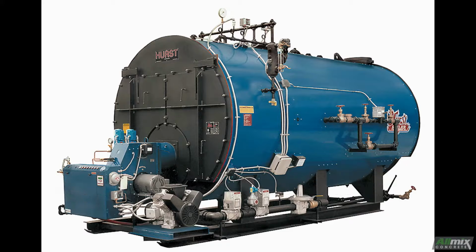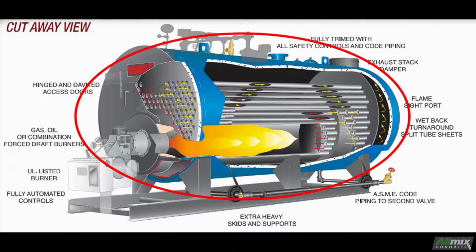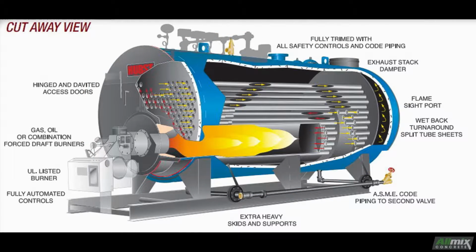The fire tube boiler, which we use at all locations, consists of the body, which contains the water and the tubes, the furnace, which produces the heat, and the preheat tank, not seen in this diagram, which prevents cold water shock and optimizes the performance of the boiler. Some plants also have a blow-off vessel to control blow-offs.